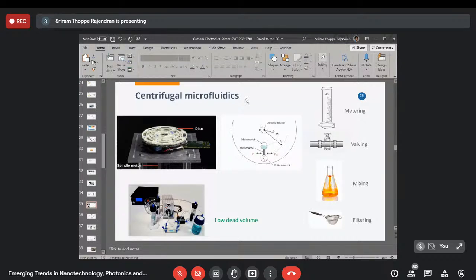In this case, instead of pushing with the pump, you load the liquid in the center of the disc, and as it spins, the liquid comes out. So centrifugal microfluidics does exactly what the typical microfluidics does. That is metering, which means you can measure how much volume is going out. Valving means closing and opening of the liquid flow. Whenever you want to stop the liquid flow, you can stop. Whenever you want to pump the liquid, you can do it. You can do the same in the microfluidics.